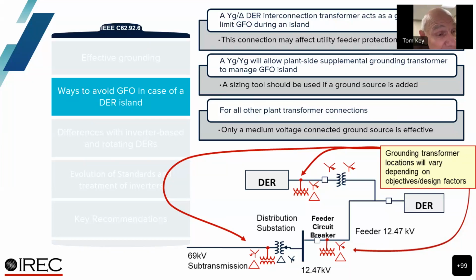So the idea is, and I think maybe 25% of the utilities require this, it used to be a little bit higher, that the DER would provide something called supplemental grounding, a connection like the wye ground delta above, and then that would be sized just for the size of the DER, and would be the way that the voltage is held down during that fault event.